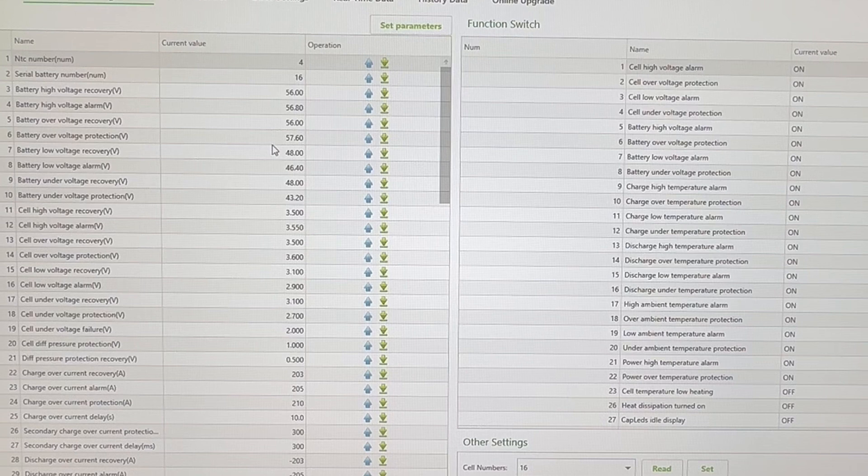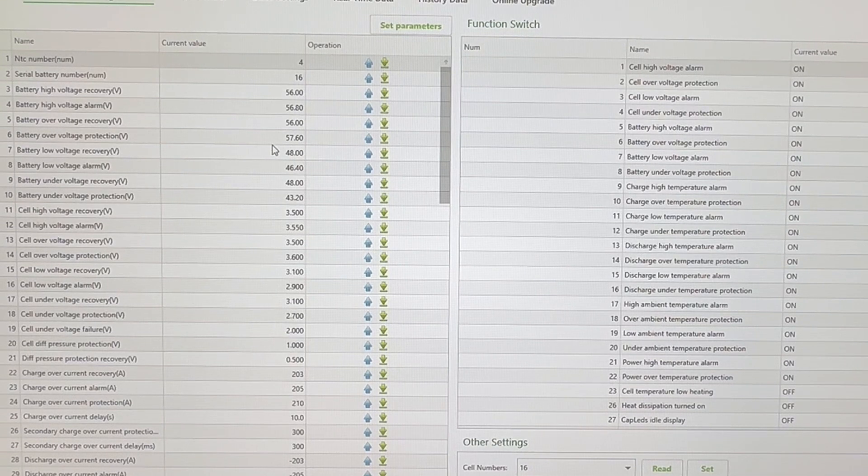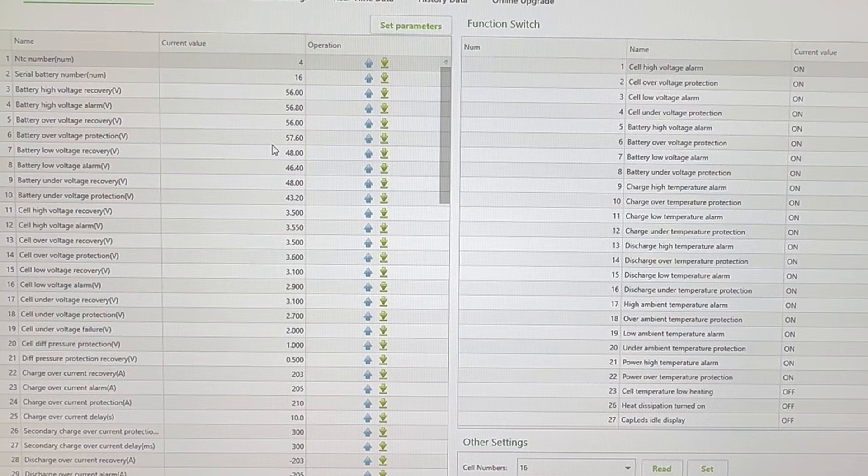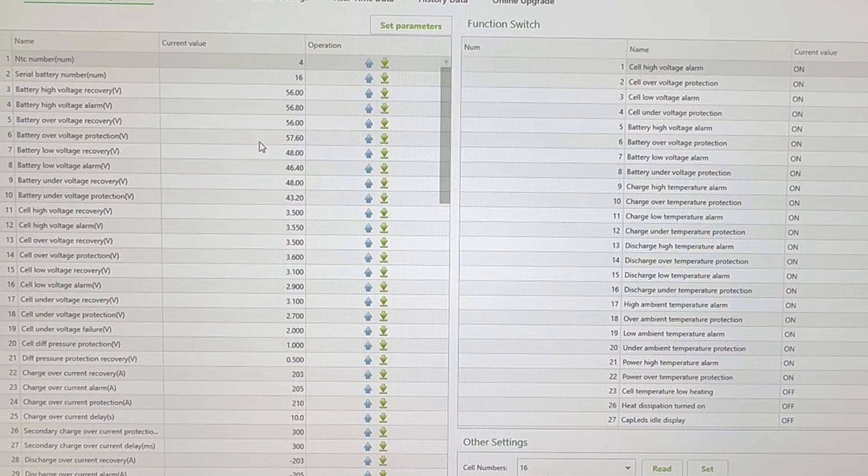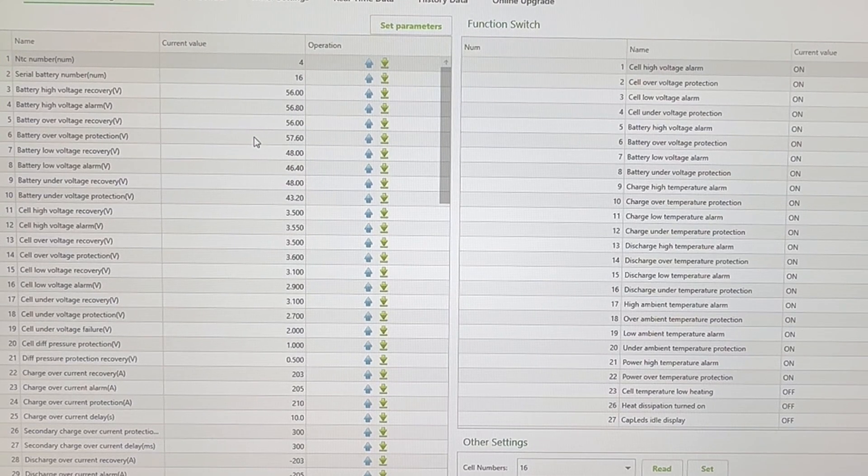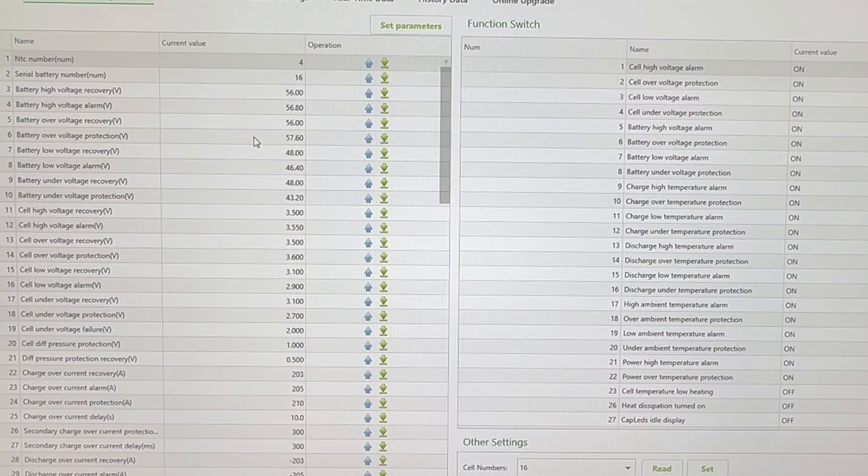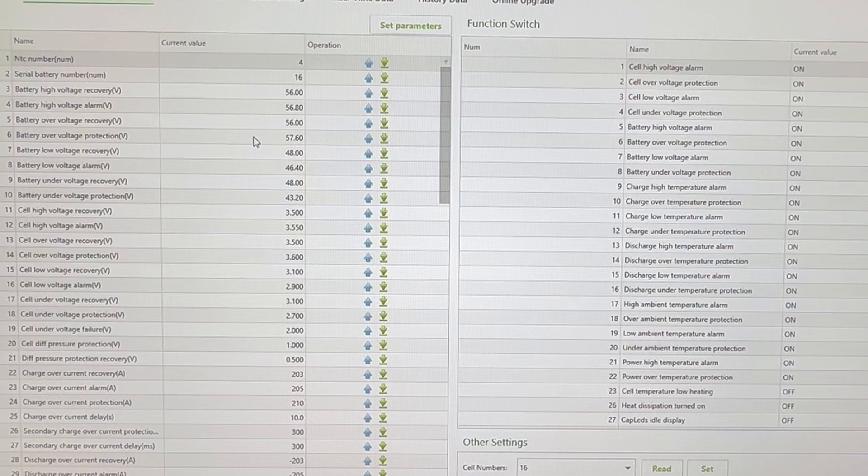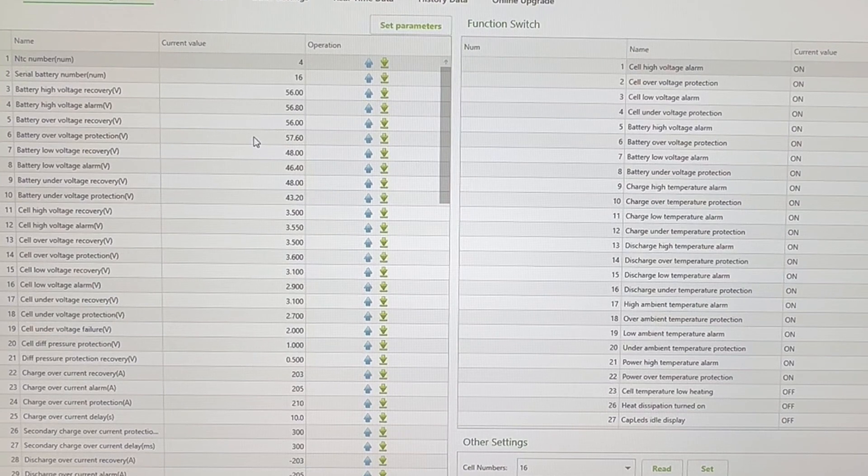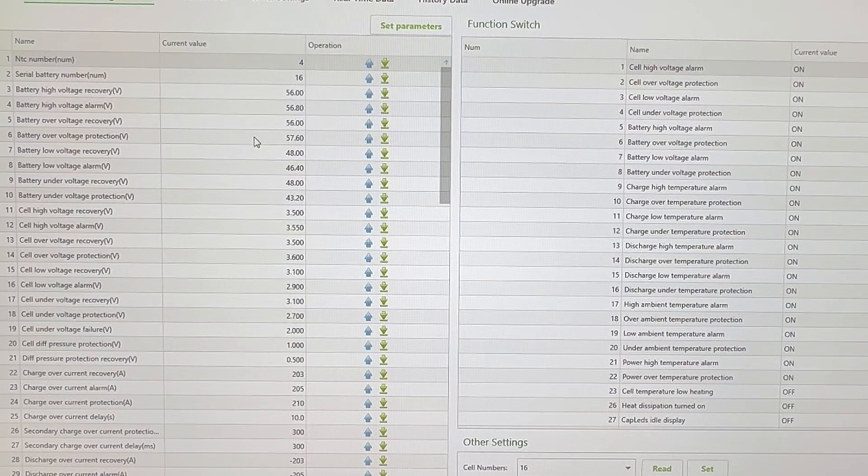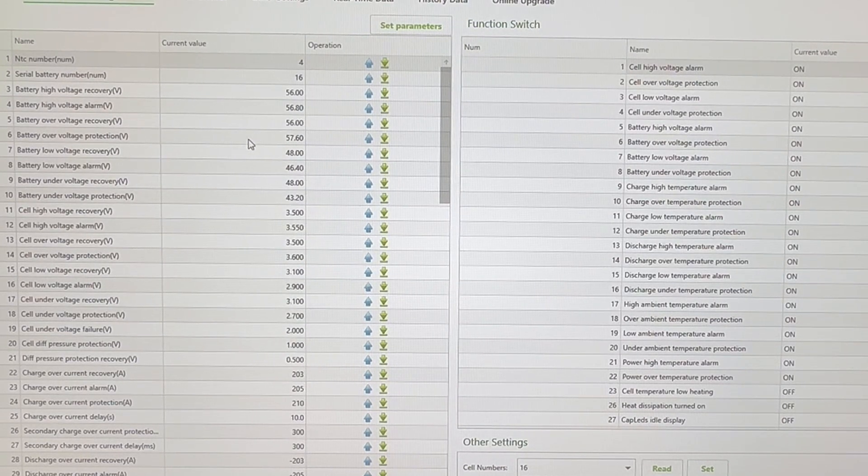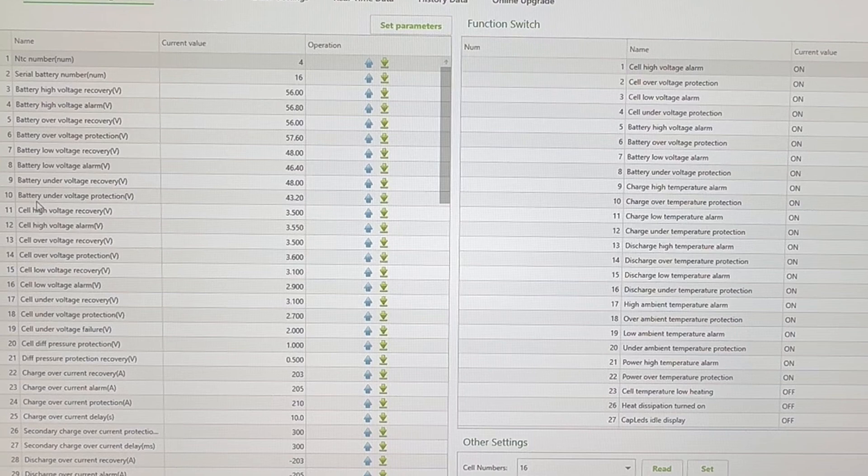Which I believed at the time was a little bit too high, but I've since been schooled, and I realized that 57.6 is actually a good figure to have. I was on a DIY solar forum, and one of the guys on there agreed that 57.6 was a little high, but doing a little more research, 57.6 for the battery over voltage protection is actually a good figure to be on.